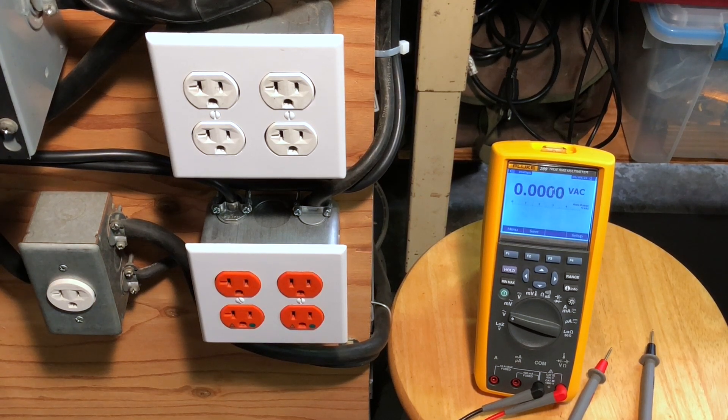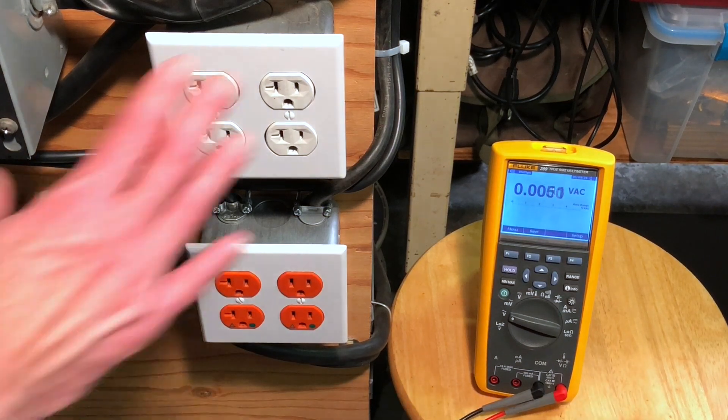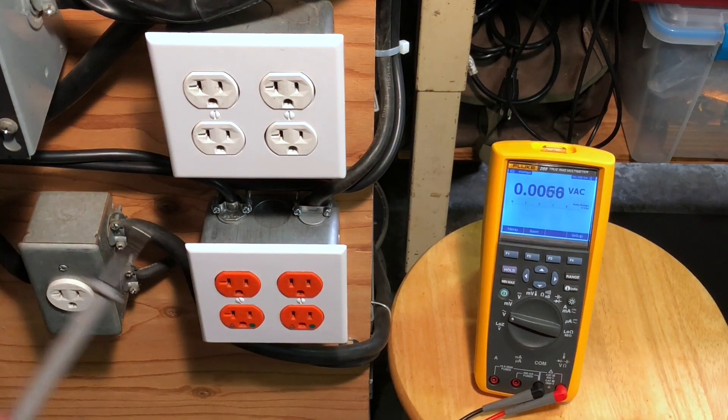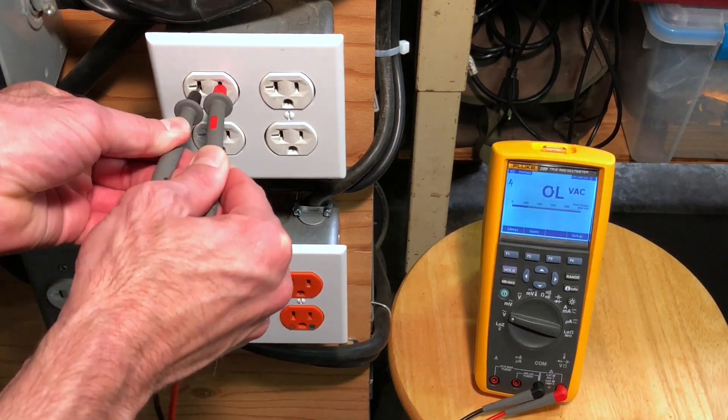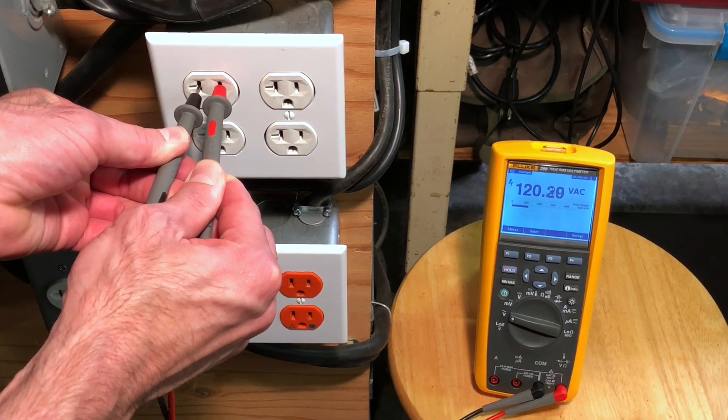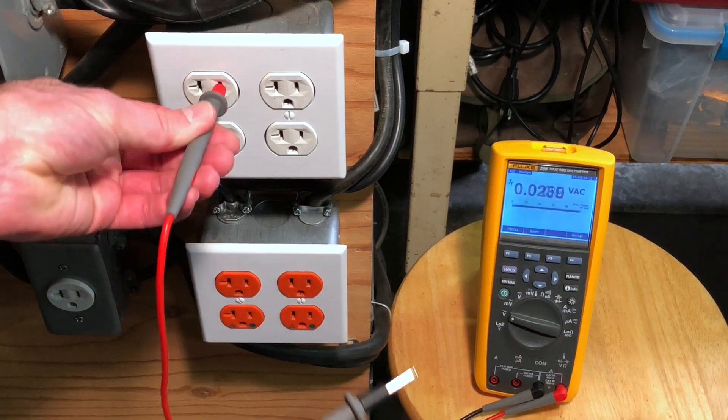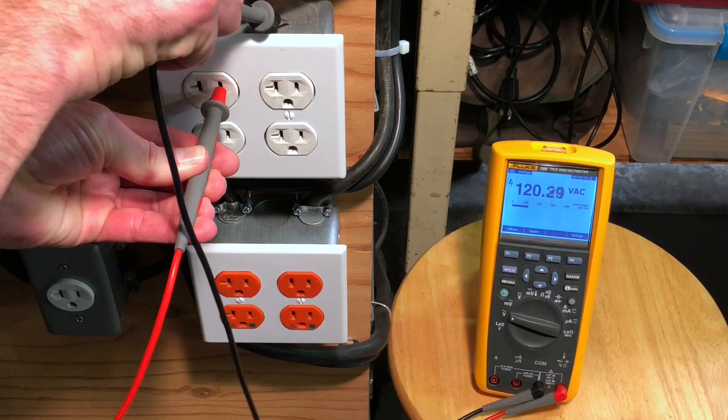Let me grab my Fluke 289 sitting right here with these test probes and take a few voltage readings around here to see what's going on. If I just probe into the outlet like so, you can see we have right there 120 volts, exactly what you'd expect. If I keep from the neutral and go to earth ground right here, nothing, and that's perfectly correct.